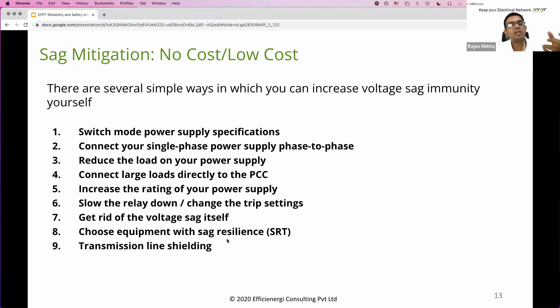in which case you probably need to do it at the equipment level. Say you have this drive, which is your point of concern, experiencing certain malfunctions or failures. That's where you will install mitigation equipment, a voltage sag mitigation device or a dynamic sag mitigation device, whatever you call it; there are different names for it. Or it can be for a group of equipment. It can be at the entrance of the entire plant, which is a costly proposition, but sometimes that's the only option.